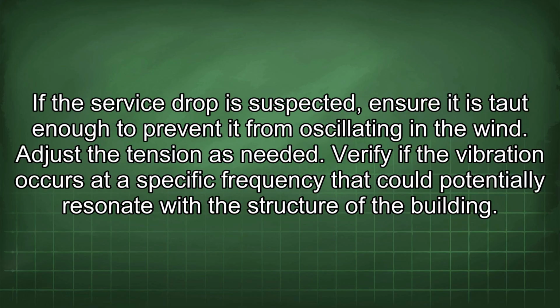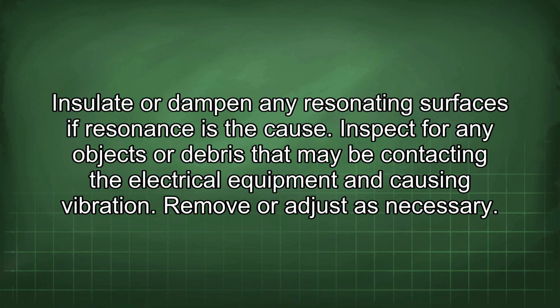If the service drop is suspected, ensure it is taut enough to prevent it from oscillating in the wind. Adjust the tension as needed. Verify if the vibration occurs at a specific frequency that could potentially resonate with the structure of the building. Insulate or dampen any resonating surfaces if resonance is the cause. Inspect for any objects or debris that may be contacting the electrical equipment and causing vibration. Remove or adjust as necessary.